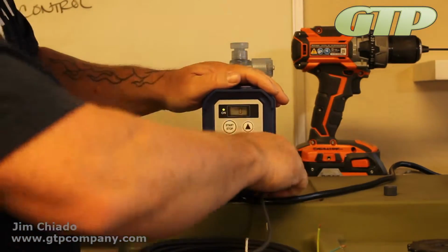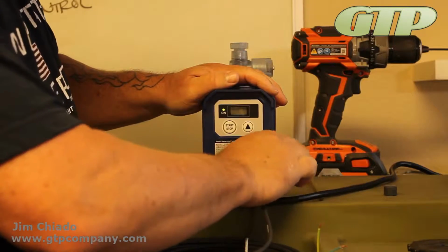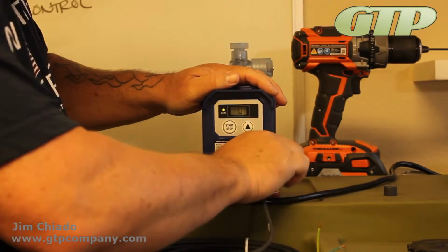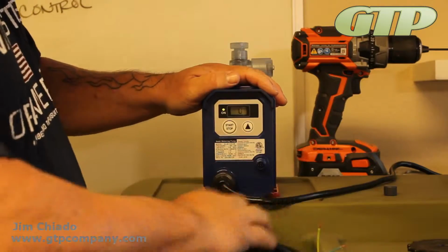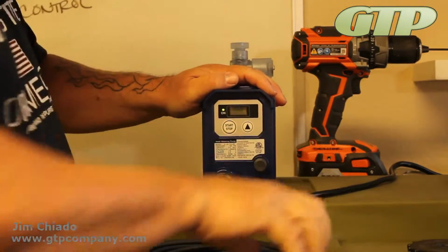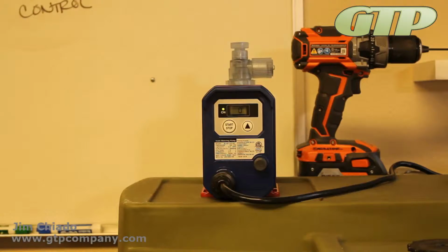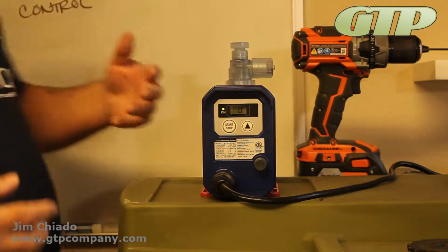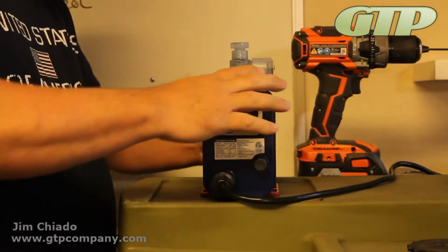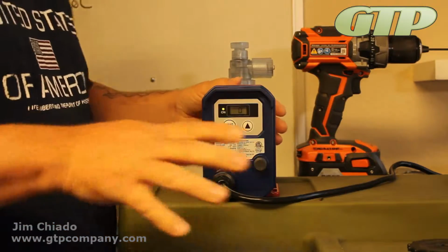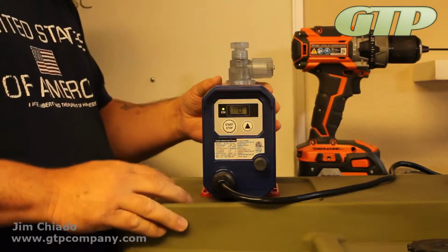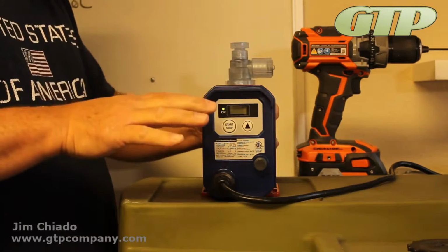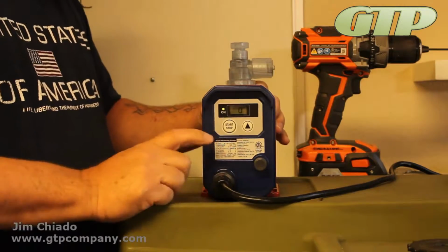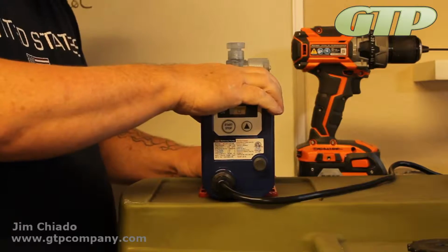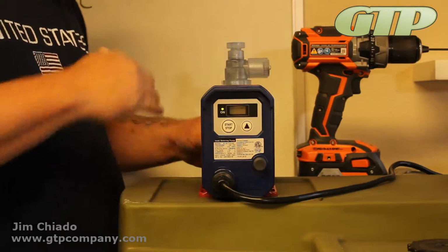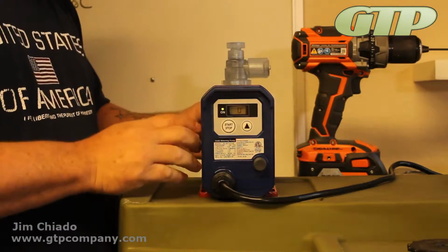So what we're going to talk about here is maintenance on a metering pump. Basically, every once in a while, just because you've got a really harsh environment here, pumping directly attached to chemicals and things like that, you do have to maintain these. Now, spare parts kits, $40 to $50 minimum, help the pump rejuvenate. Those are your wear items too, not really part of warranty, but replaceable. They make the pump perform much better, back to factory specs.